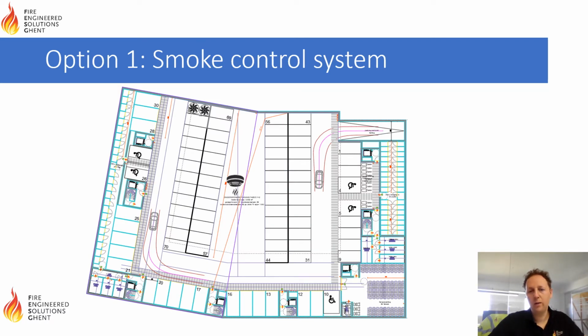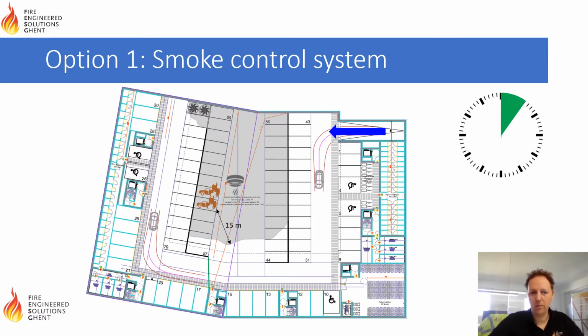The first option would be to put a smoke heat control system in place, which would be designed on 2 or 3 burning cars. So basically based on the fire detection, which could take place between 1 and 5 minutes depending on the type of detection system, the requirement would be to have a smoke-free access up till 15 meters of the burning car for a period of 15 minutes. So if the fire brigade intervenes in the first 15 minutes, there is a smoke-free access till 15 meters. If the fire brigade arrives later, there is no requirement in terms of smoke-free access.